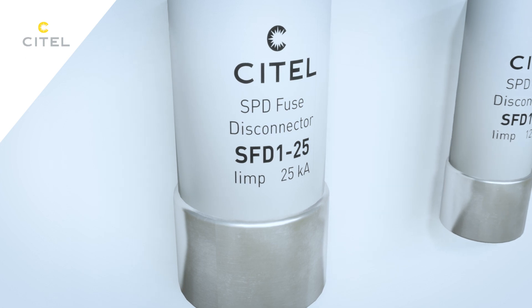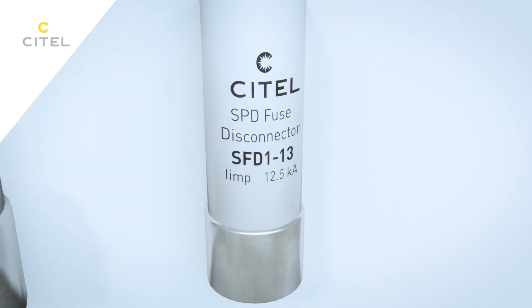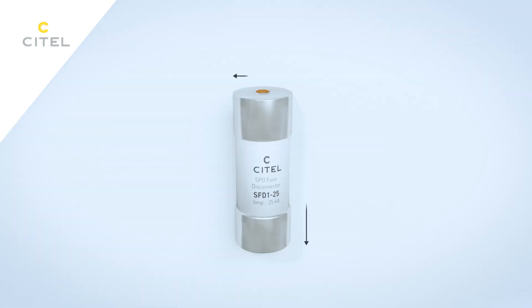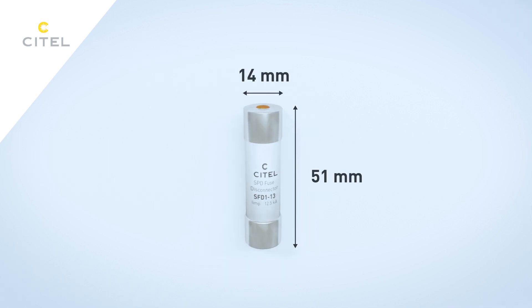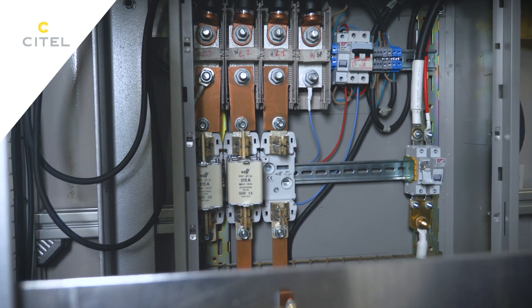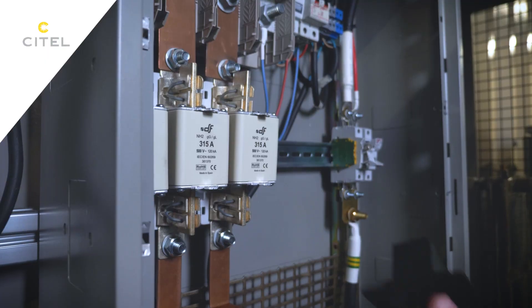SFD1-25 can conduct 25 kA in 10/350 microseconds. SFD1-13 conducts 12.5 kA. SFD1-25 fuse has a 22x58 mm size, while SFD1-13 has a 14x51 mm size. Compared to NH fuses, the dimensions of CITEL SFD fuses are reduced for easier installation and use.